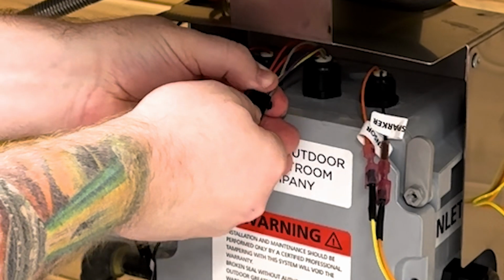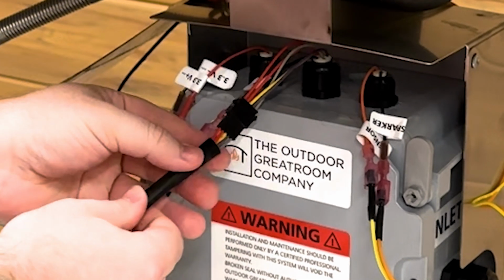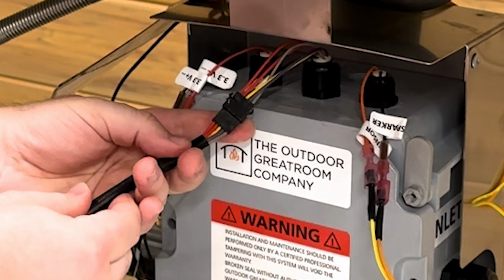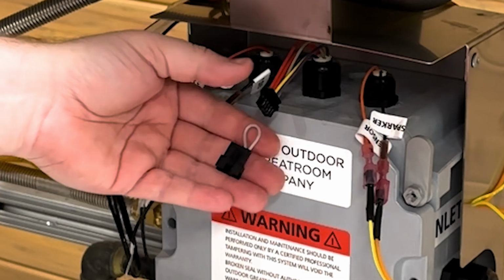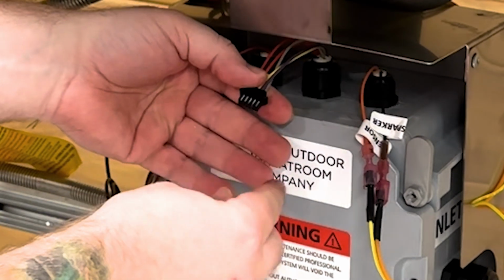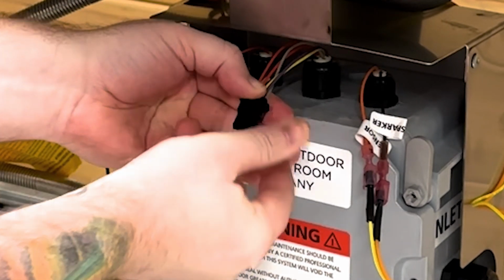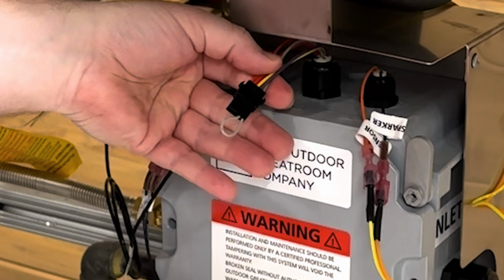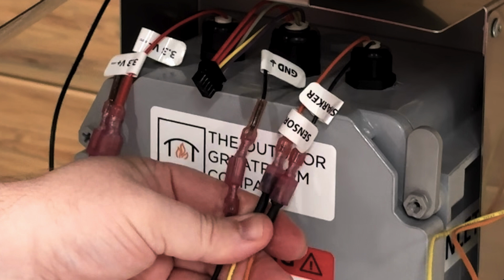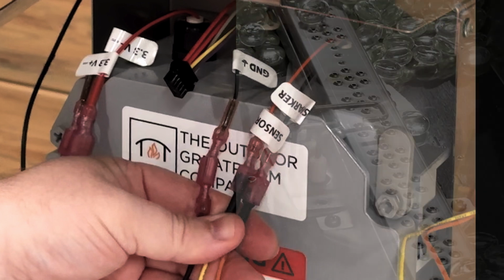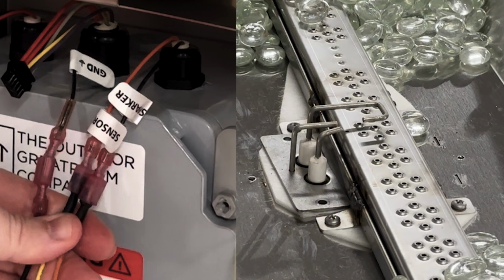Connect the 5-pin connector coming off the electronic ignition box to the 5-pin connector coming off the on-off switch of the unit. If you desire to not have a switch on the unit, you will simply install the switch bypass as shown here to allow you to switch the burner away from the pit by controlling the power to the outlet which the transformer is connected. Verify the wires labeled sparker, sensor, and ground on the electronic ignition box are connected to the sparker, sensor, and ground wires coming off the burner. These connections should have been pre-made at the factory.